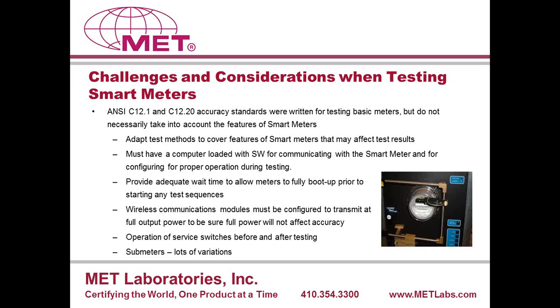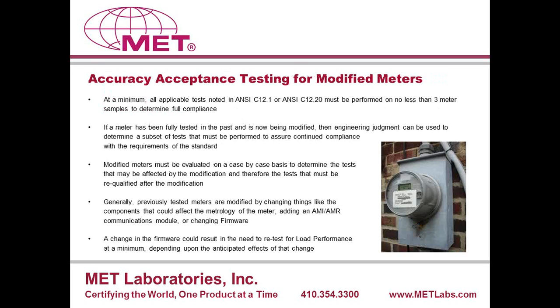Submeters. Is it a submeter? There are a lot of variations there, and these standards were not written for submeters. But having said that, the public service commissions and other folks out there that are knowledgeable in meters and want to see the accuracy of submeters tested to something, they refer back to the ANSI C12.1 standard. So, with all the different variations of meters, it's a lot to consider what would be applicable out of that standard. How would we go about configuring for test and that sort of thing? Is it a direct connect submeter? Does it have CTs? Does it have VTs? That sort of thing. All this has got to be considered. So there's a lot of challenges and considerations getting into a test program.